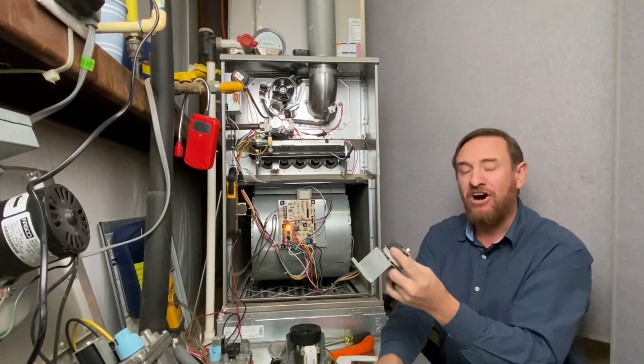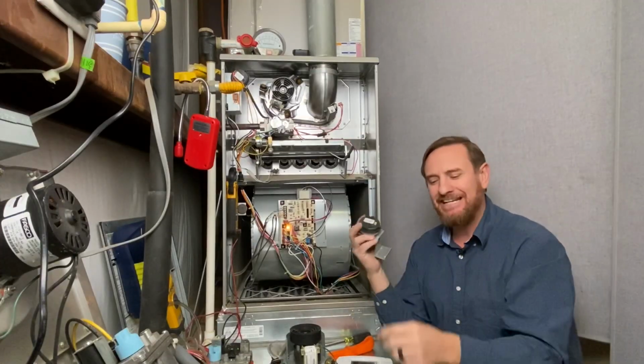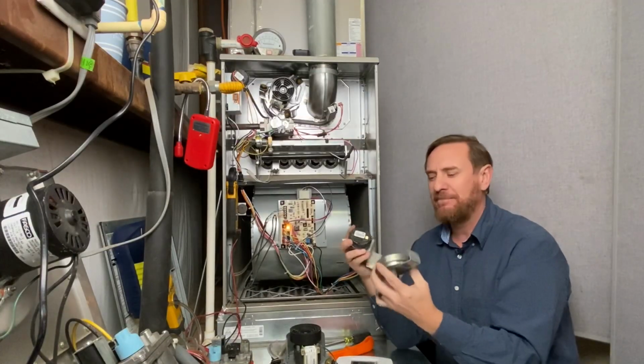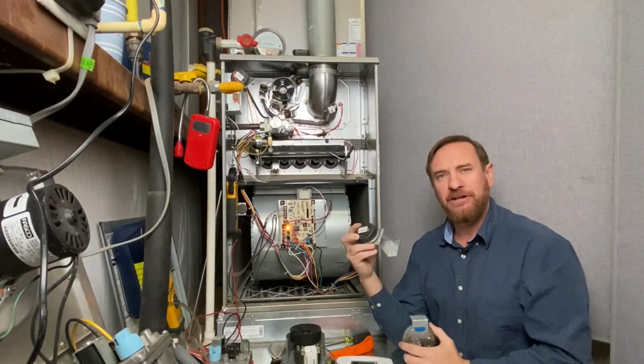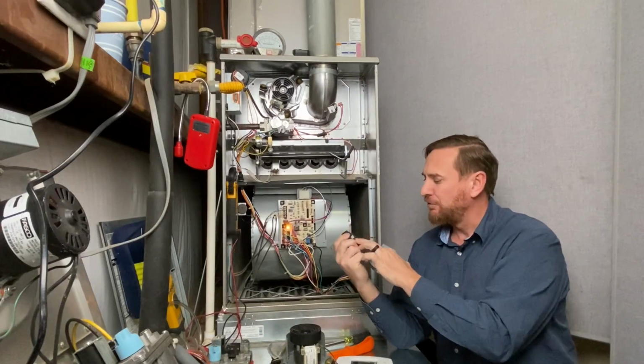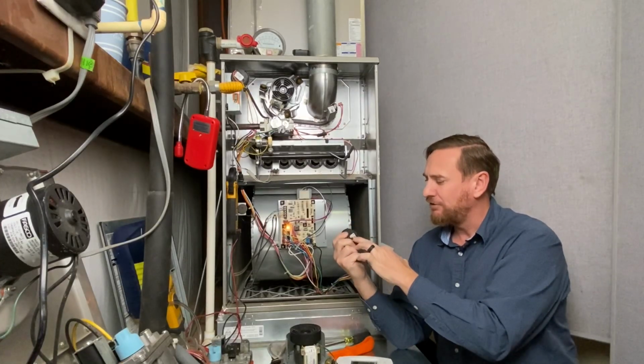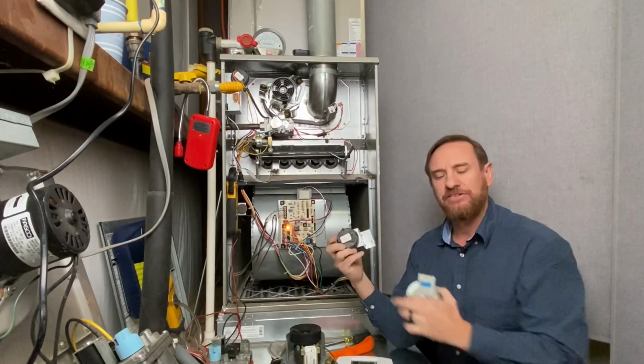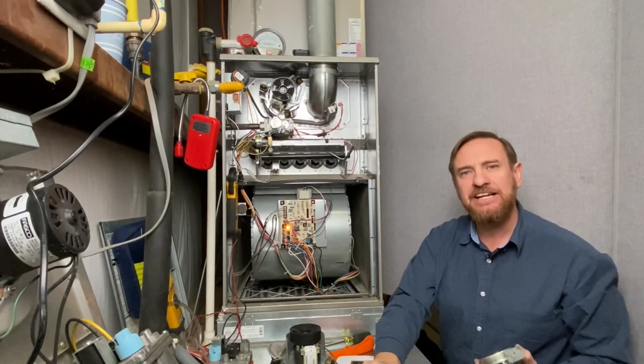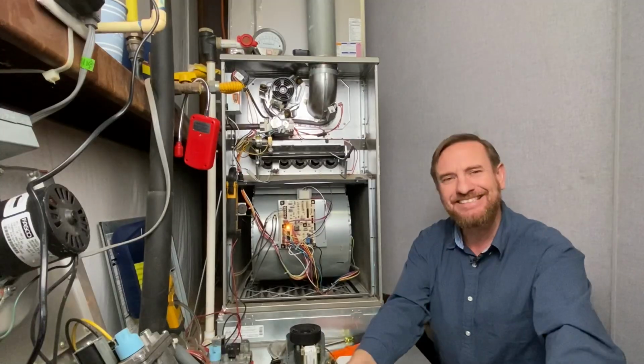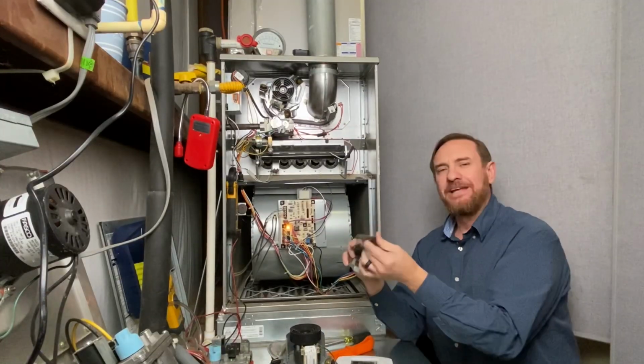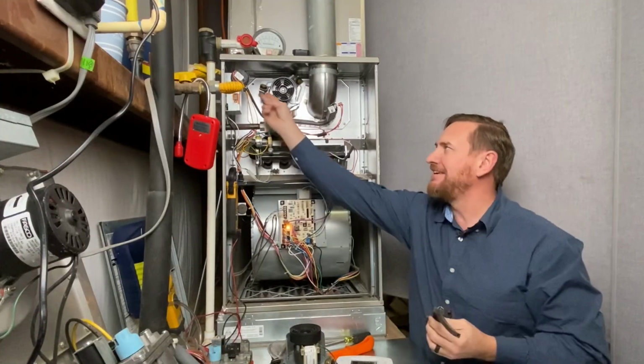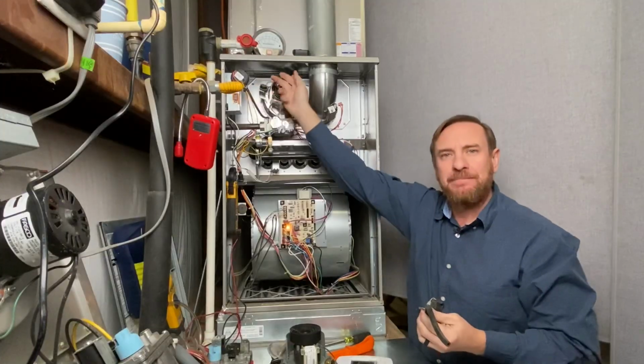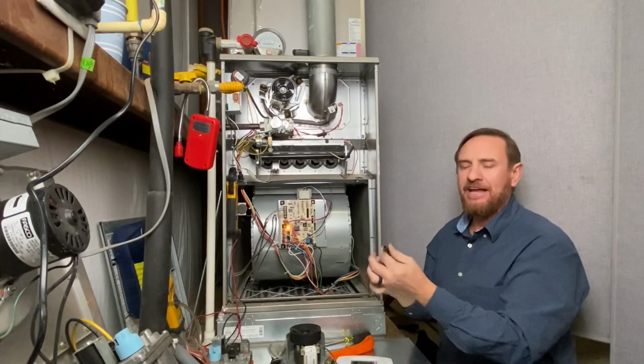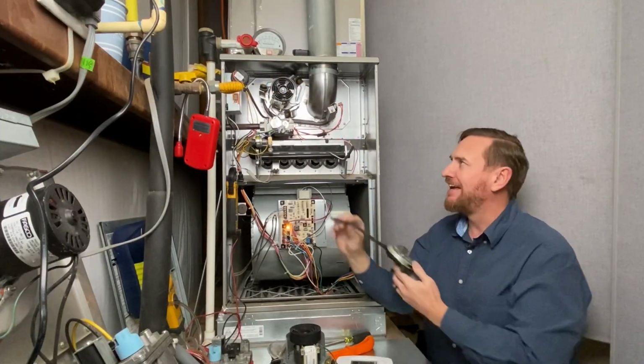Now, on that, you can't just replace any one of these, even though they do the same job. They have different pressures that they open and close with. This particular one here breaks at 0.27 inches of water column, and it makes at 0.42 inches of water column. So they have different settings when they open and they close by design. So there's a way to test this. You can actually put a T in this hose, or you can keep a spare set with you with a T on it, and you can check the water column on that while the system is running.